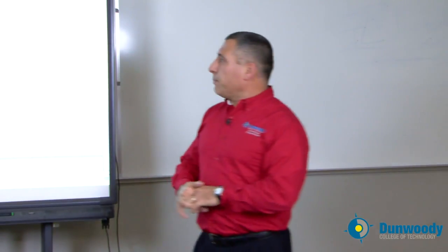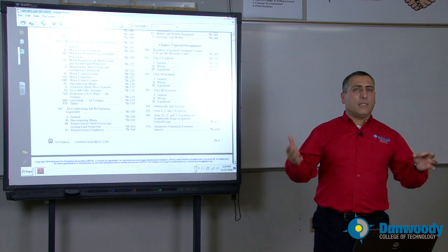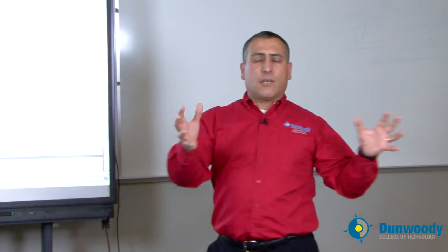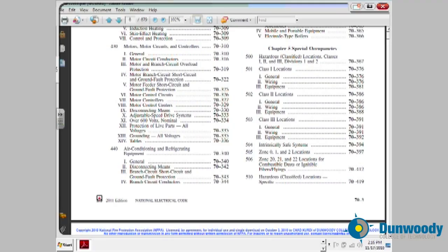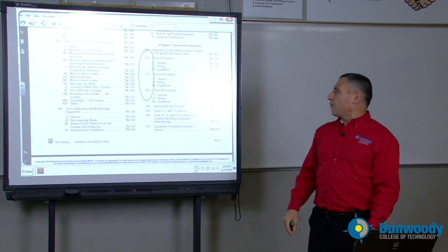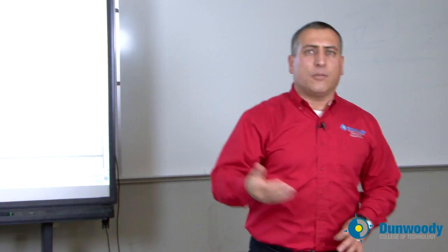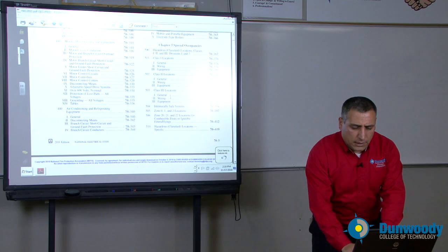Moving into chapter five, which talks about special occupancies. If you are doing commercial or industrial work, especially industrial, you're going to be involved in hazardous locations — gas stations and so forth. How do you wire a gas station? That's definitely different than wiring a shed in your backyard. Highlighted topics include class one, two, three locations — explosive and flammable gases — and you cannot install an EMT conduit in a class one, division one location.